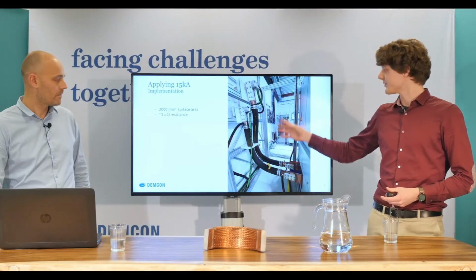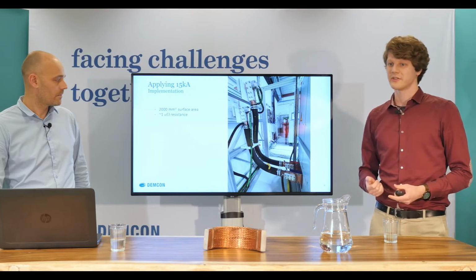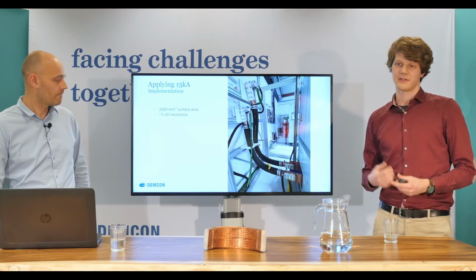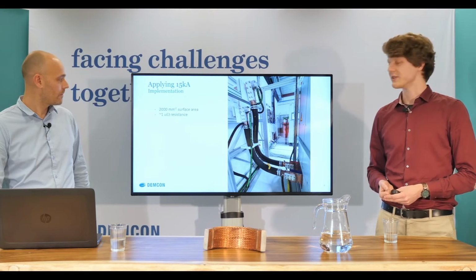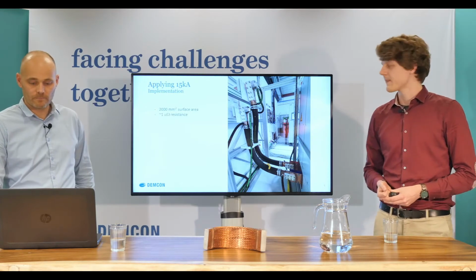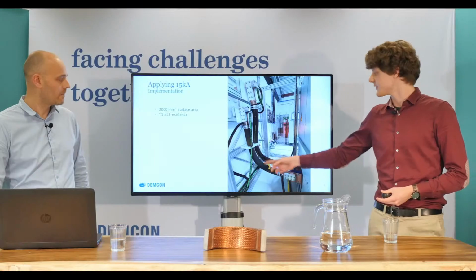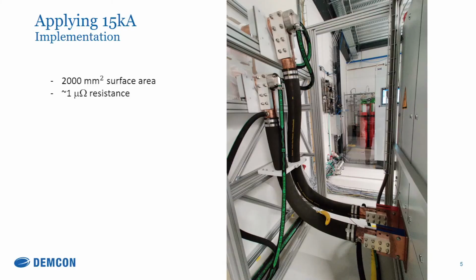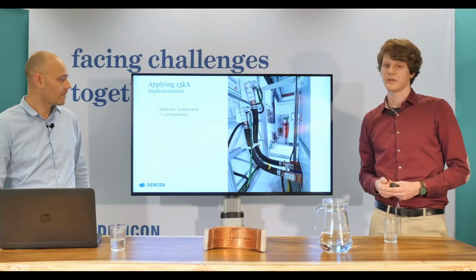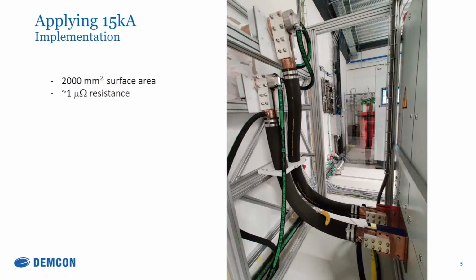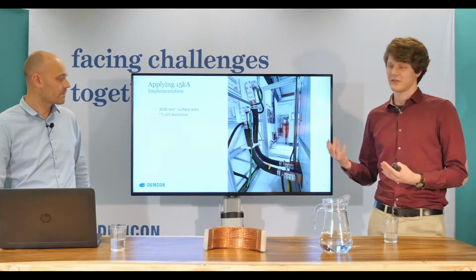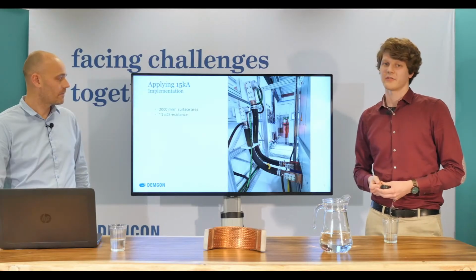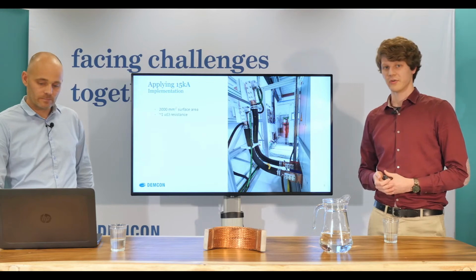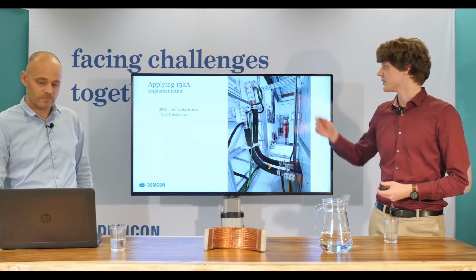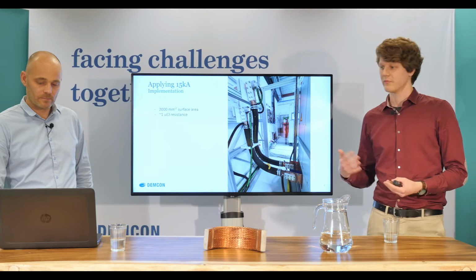The surface area of these cables is about 2000 square millimeters, and therefore the resistance of these cables is only about a micro ohm. Furthermore, you can see these cables are water cooled, and some silver connections are attached. That is because the contact resistance of two copper parts attached to each other is actually so high that we needed to be careful about the heat generation on these contacts, and therefore silver plating some components was the solution.